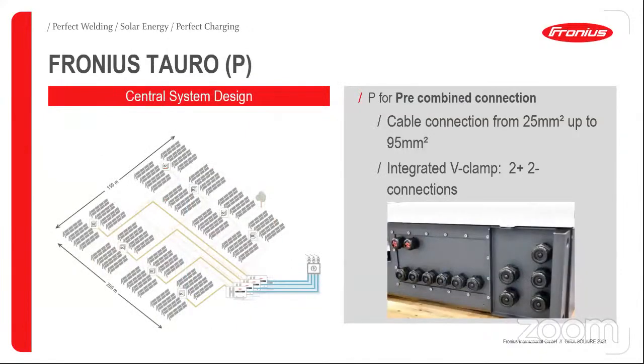In the Caribbean, sorry. Also, we have the option to use this Tauro inverter for central design, this type of typology, when we can collect and connect all the inverters very close, maybe in one single roof of inverters. And in this way, the best option to save a lot of money in the BOS of the system is to reduce the amount of DC cabling. We know that is something very expensive in most of the cases. So what we are doing with this P version of the Tauro is to allow the connection of the DC side cabling up to 95 millimeters. So you see here the difference. We now don't have here a single connection, but we can enter to the inverter with a bigger cabling, which reduce the losses in the transport, but also reduce cost in the BOS due to this cabling.